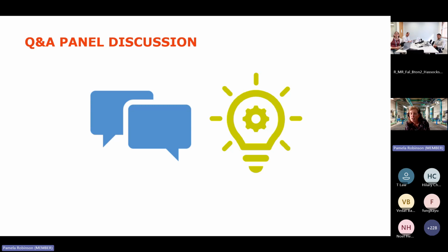Thank you, Chloe. On the line pressure driven control valves, I think it's one of your slides, Sam: are there issues with controlling the system under cooler conditions, where freezing could occur? Yeah. So these valves are usually installed in chambers, so there is a degree of protection from frost in that respect. But it's always worth doing your trace heating and lagging assessment. I think the valve manufacturers offer some sort of additive that can be put into those lines. And it's also worth stating that due to the small bore pipework, they're susceptible to contamination. So any particulates that work their way into the pilot tube system can affect the proper operation of those control valves.